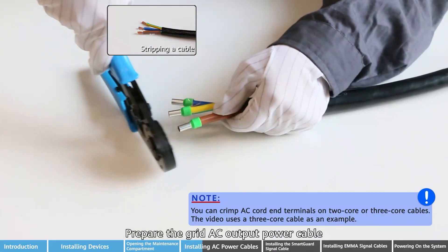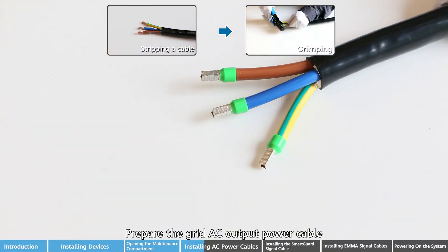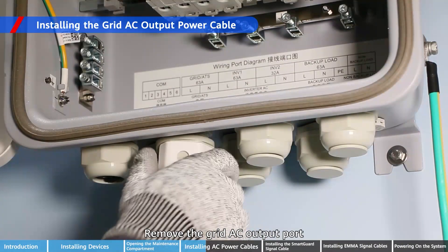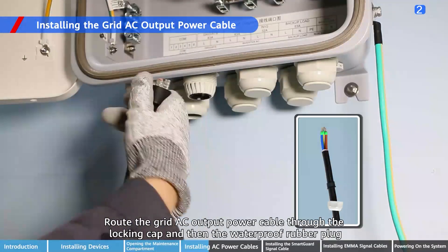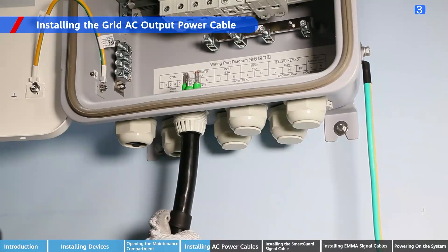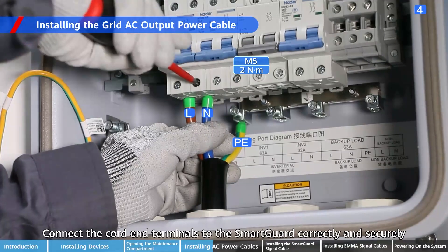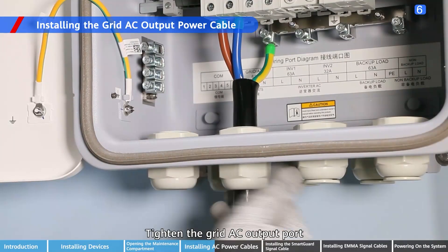Remove the grid AC output power cable and the grid AC output port. Route the grid AC output power cable through the locking cap and then the waterproof rubber plug. Connect the cord end terminals to the SmartGuard correctly and securely, then tighten the grid AC output port.